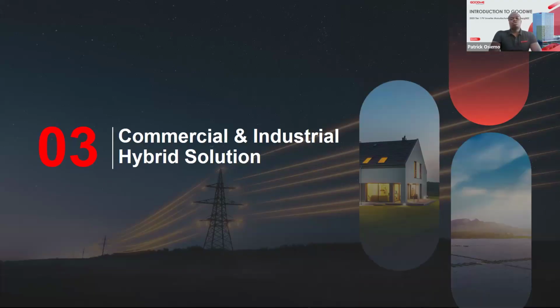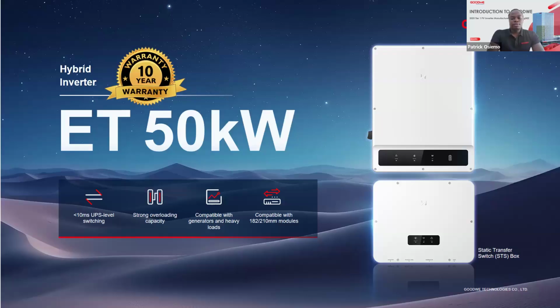Now, I would like to introduce you to the commercial and industrial hybrid solution that we also offer, which to begin with, is the 50 kilowatt hybrid system. The 50 kilowatt three-phase hybrid inverter, we usually couple it to the STS, which is a static transfer switch. With that combination, you have less than 10 millisecond UPS-level switching. That is seamless switching. Your critical loads will not sense any power outages from the grid side. We also have a strong overloading capacity. For our 50 kilowatt, we have up to 75 kilowatt surge support, and we are compatible with heavy loads and diesel generators.